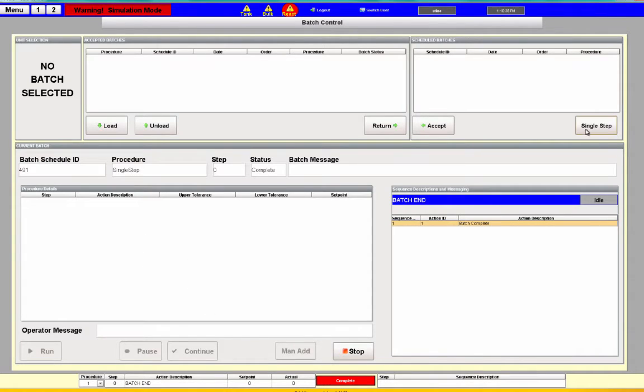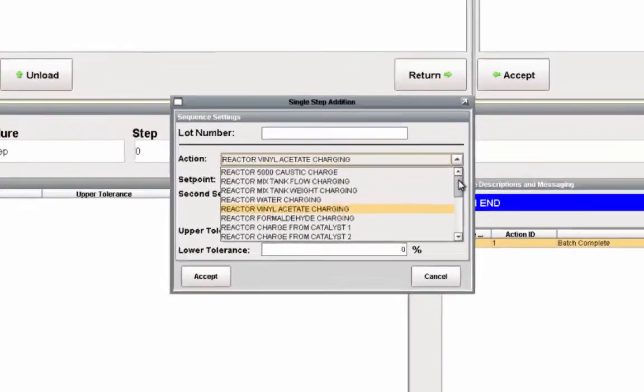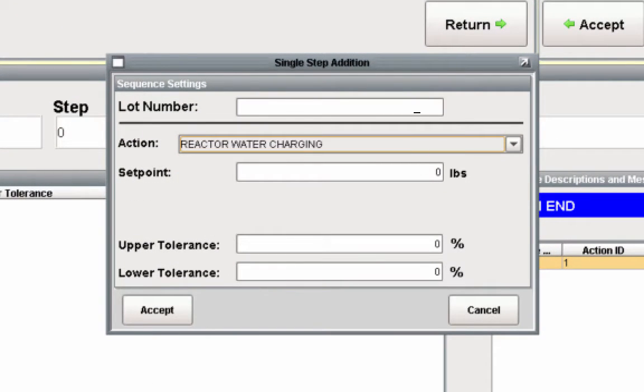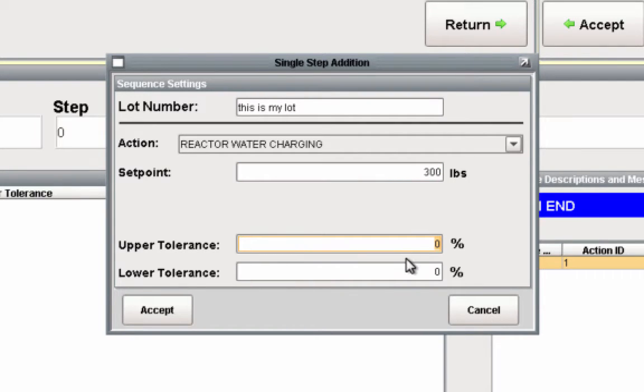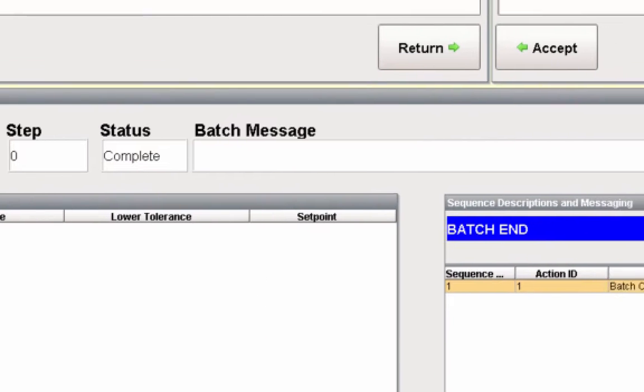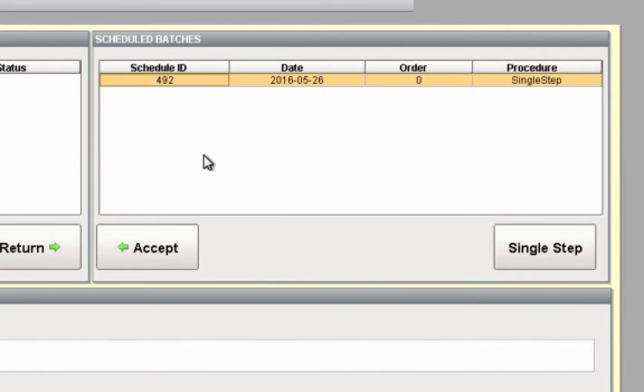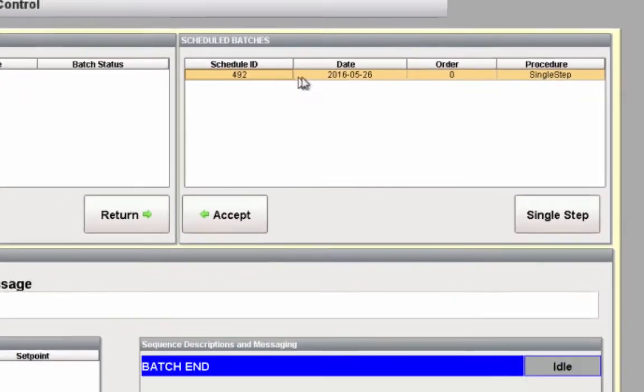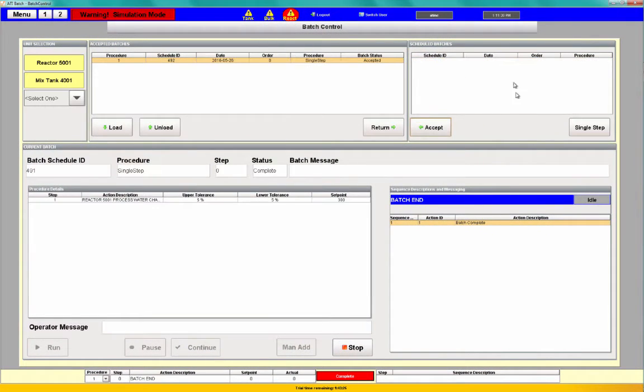I can also do what's called a single step — I can run a single sequence if I'd like. So all I have to do is come in here and select water charging. We'll put a lot number in there, say we want 300 pounds of that with a tolerance of maybe 5% on either end. I've added a little mini batch procedure. This batch procedure only has one step, and once accepted, it will appear as a scheduled batch.